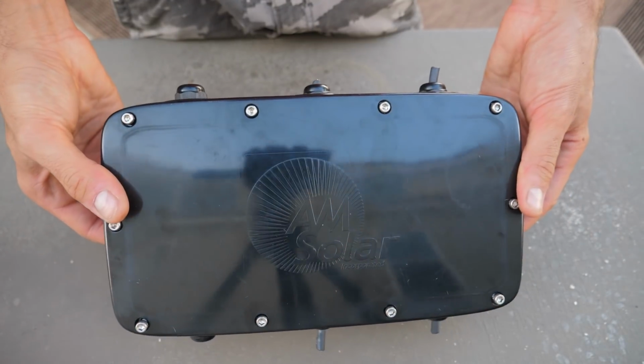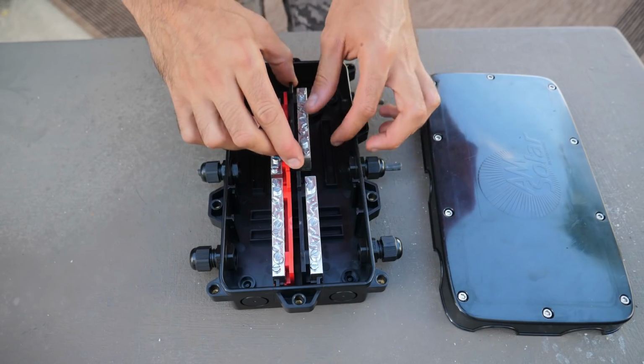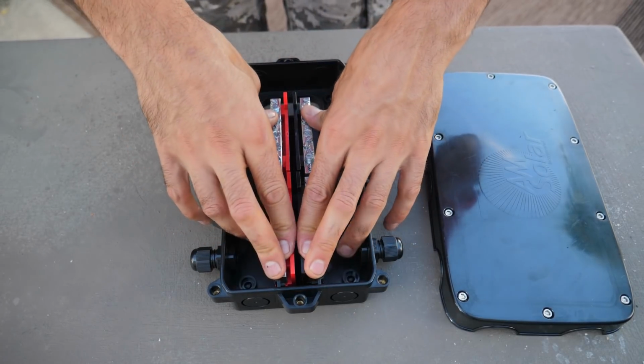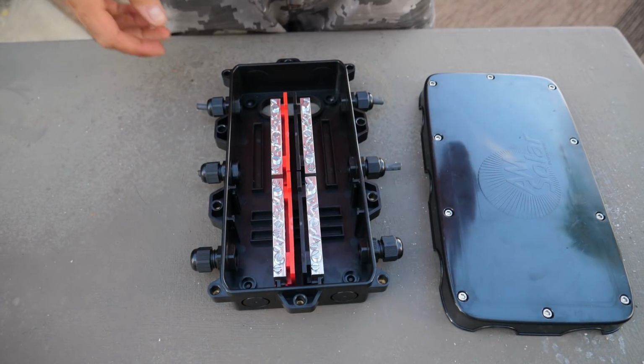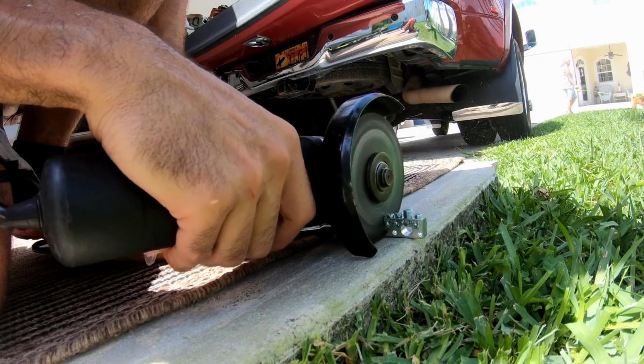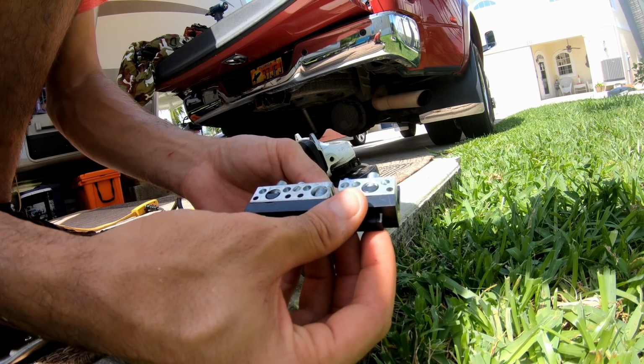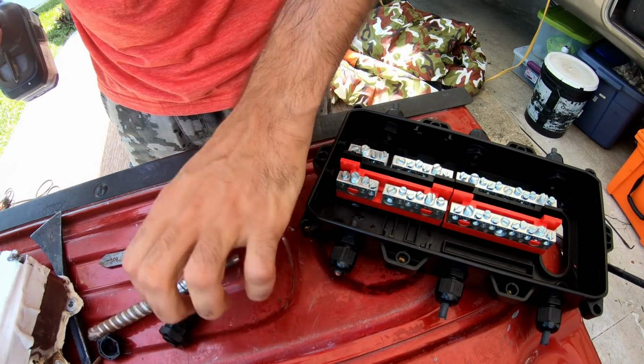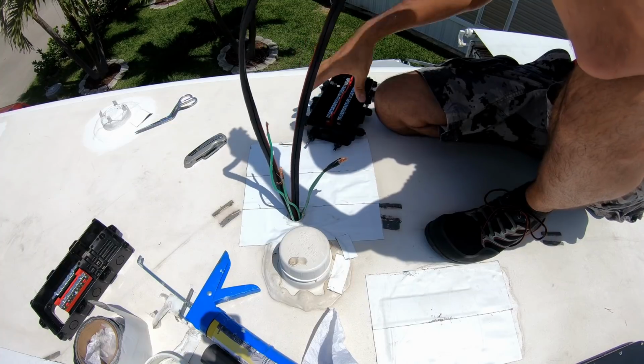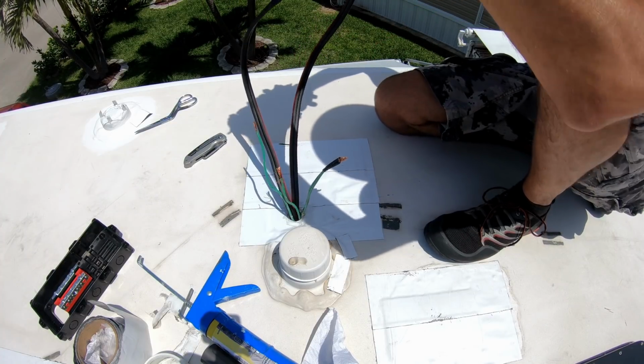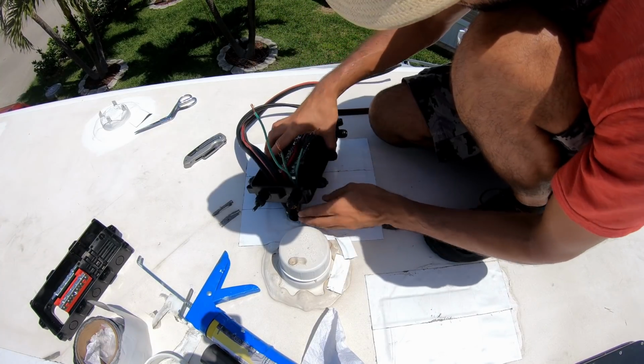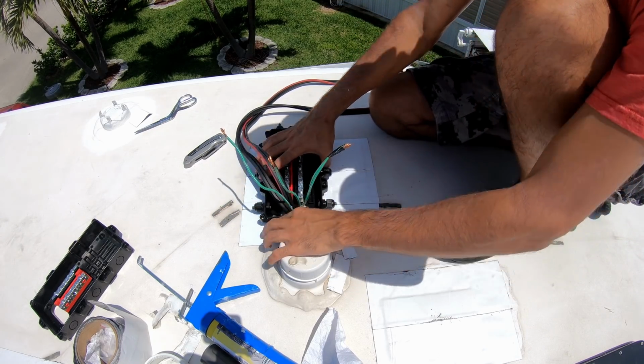We decided to use a dedicated low-profile solar combiner box on the roof that already had two independent bus bars for separate charge controllers. We modified the junction box slightly, splitting one of the bus bars to allow three separate circuits. We installed the junction box on the roof, wiring our leads that would run down to the batteries to each bus bar that we'd later connect the solar panels to.